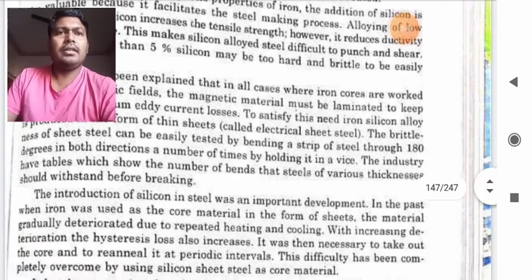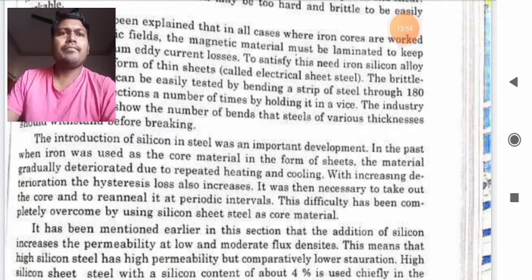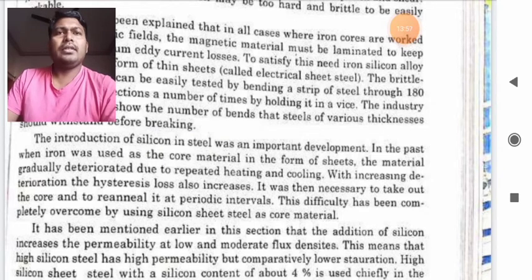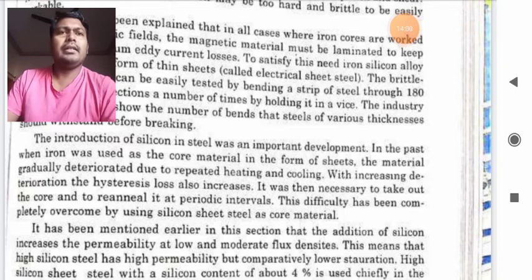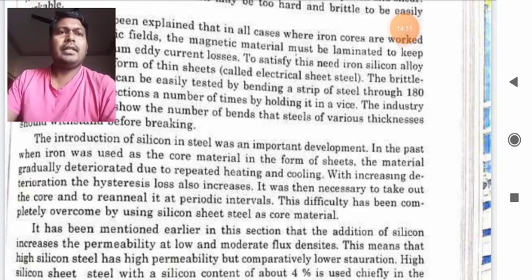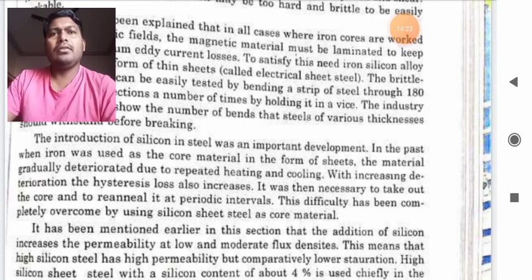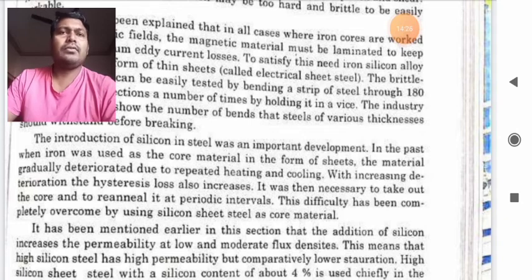The introduction of silicon in steel was an important development in the past when iron was used in the core material in the form of sheets. The material gradually deteriorated due to repeated heating and cooling. With increasing deterioration, the hysteresis losses also increase. It was then necessary to take out the core and re-anneal it at periodic intervals. This difficulty has been completely overcome by using silicon steel as a core material.